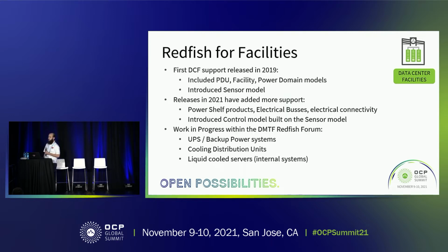For folks who don't know, there's been some data center equipment that's already contributed to Redfish and been standardized. So the work has been going on for years now. Back in 2019, we have the first facilities model that was introduced in Redfish that also included how do you model PDUs, so things like rack PDUs. How do you model your power domains in a facility? We also introduced our common sensor model for giving any sort of reading that you might envision. That's been extended over the years to incorporate new reading types as there have been use cases identified, but overall the general structures remain the same.